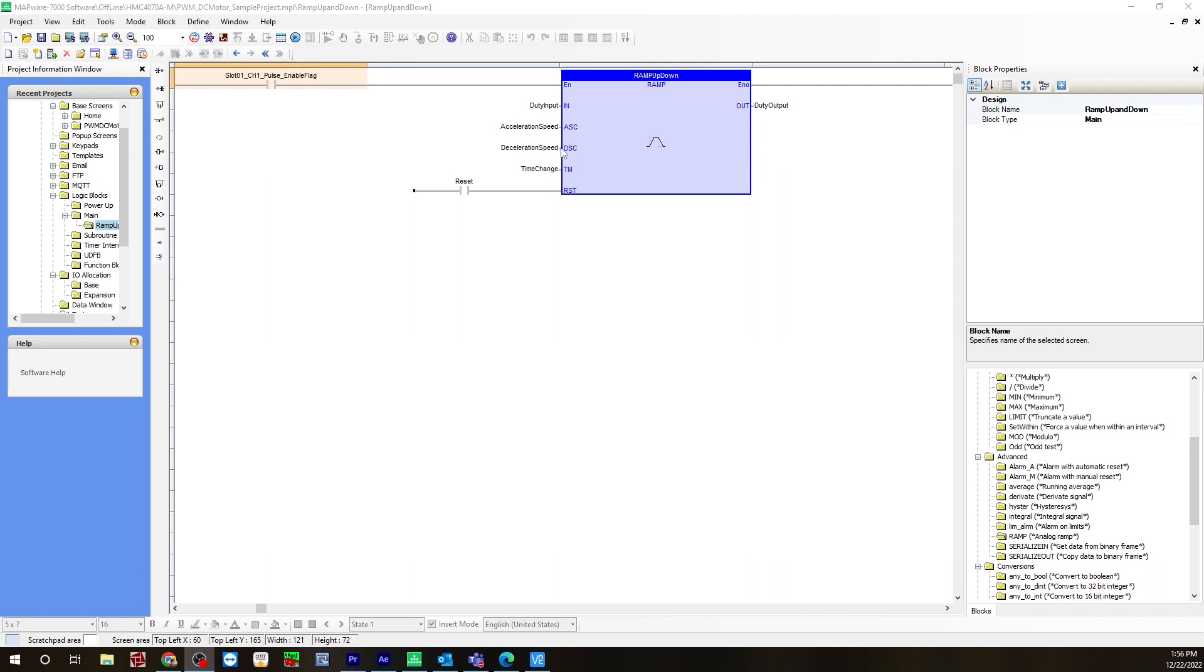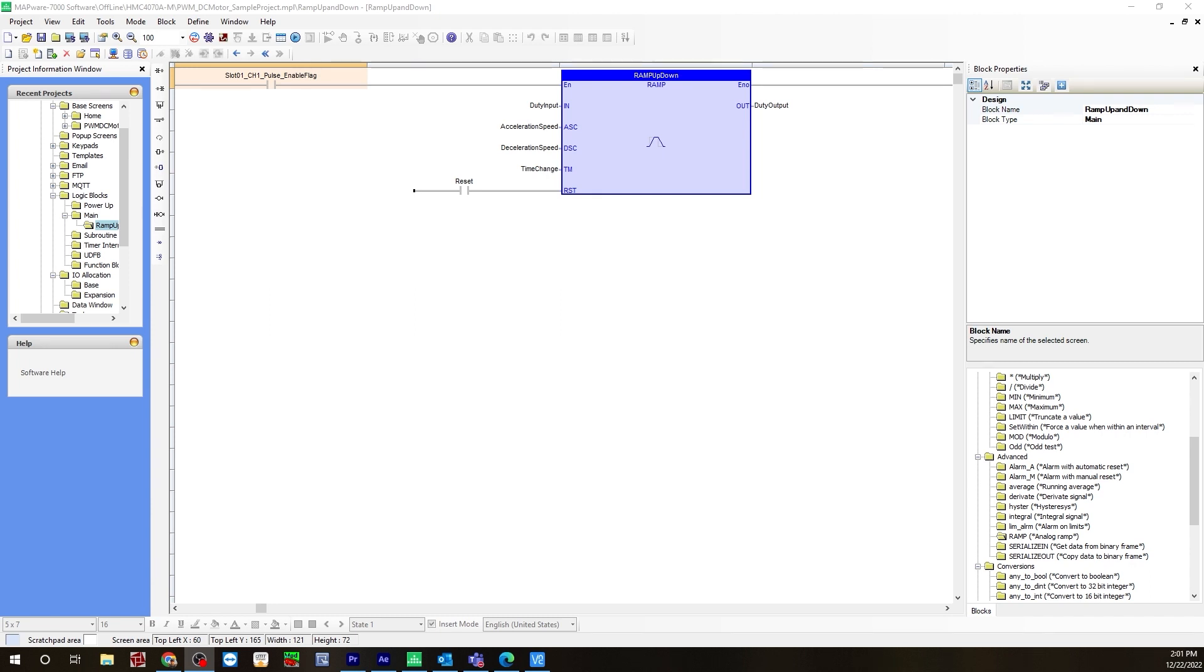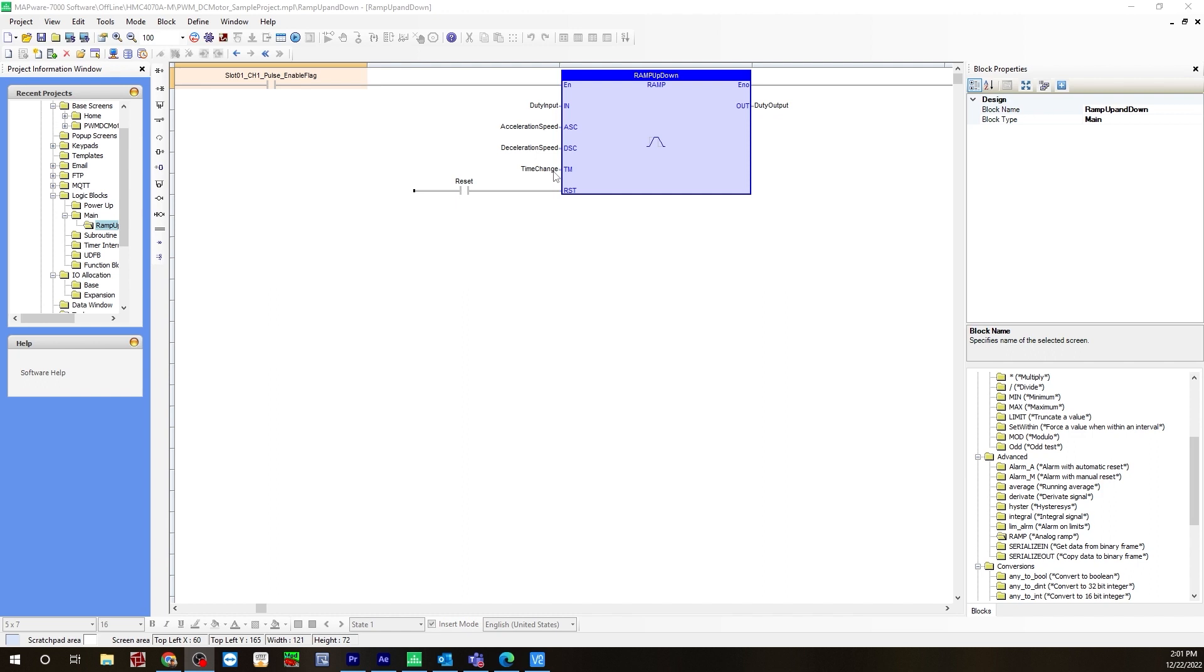Also, if you were to set the duty cycle to 50, and let's say you change the acceleration to be different than the deceleration. If you had the acceleration set to 100, and the deceleration set to 200, and if you left the time the same at 20, it would still take 10 seconds to get from 0 to 50, but it would only take half the time to get back down to 0. It would take 5 seconds. So if you think of this as the slope equation, rise over run, or acceleration over time. If you say 100 percent duty cycle over 20 seconds, that would equal 5 percent over 1 second. So it would take 1 second to go 5 percent of the duty cycle. If you think of it like that, that's a good way of determining how long it will take to get to each duty cycle as far as accelerating and decelerating.